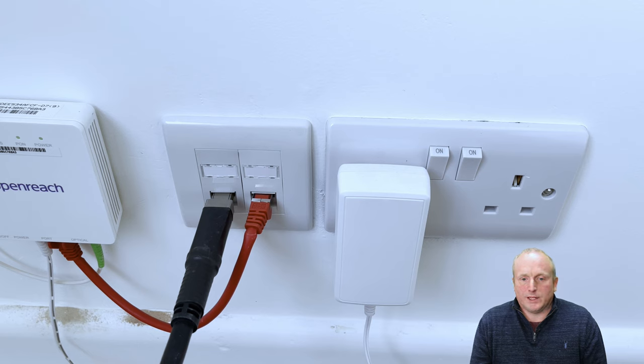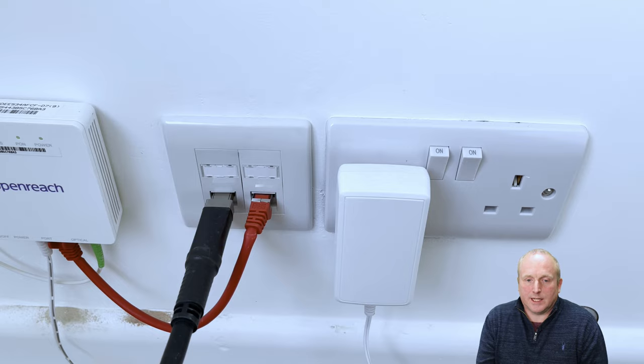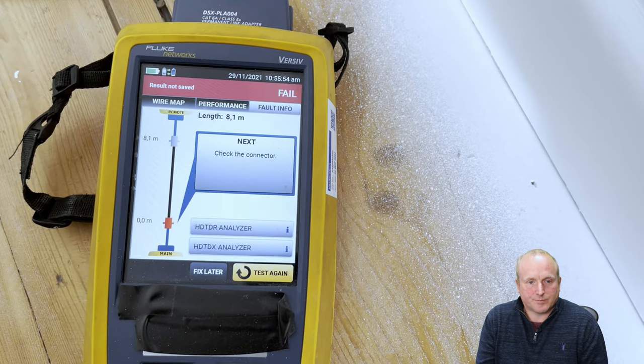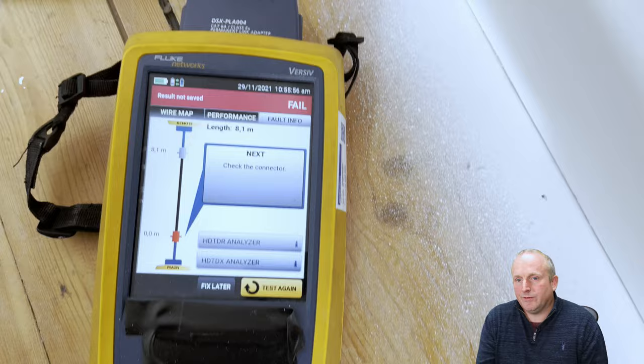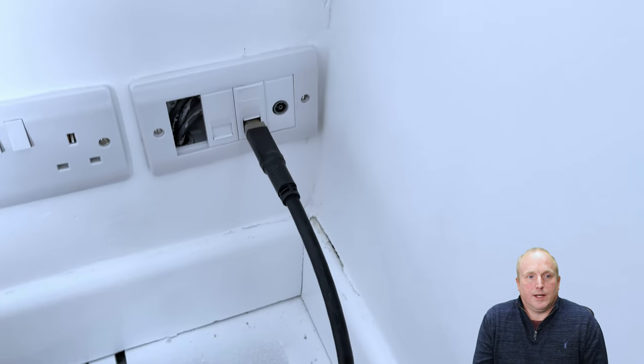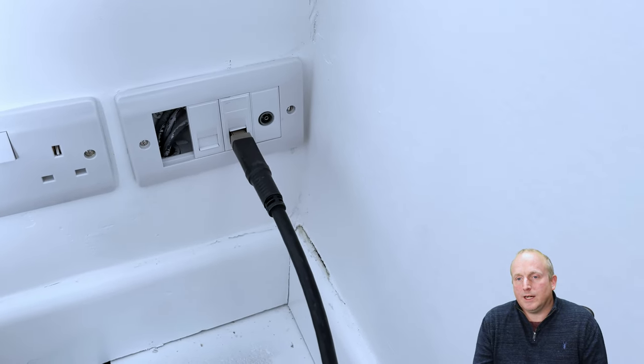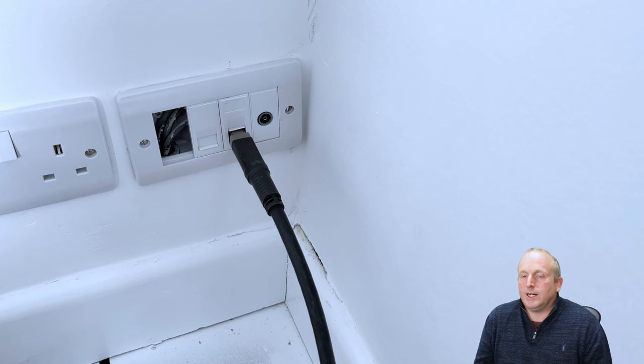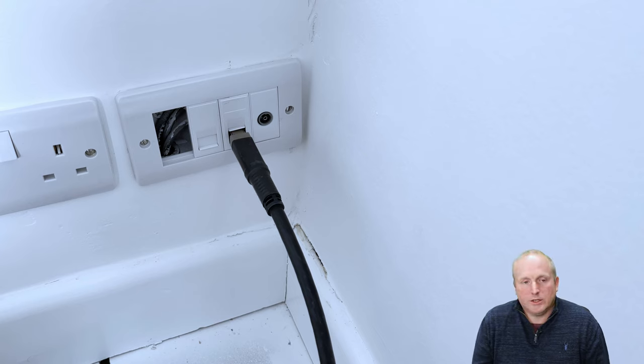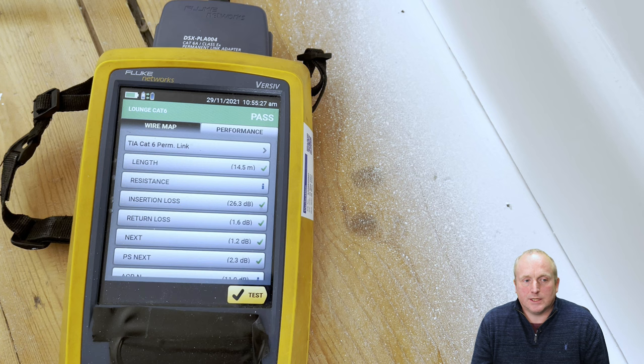One of the interesting things with this tester is it will pick up and certify. I'm going to show here another test now where we've actually done a test here. You can see this is actually failed. This is plugged into a wall socket here. That socket is actually a Cat5e socket on the end of a Cat6 installation. You'll see if I actually go back to the start of the test here and run the test.